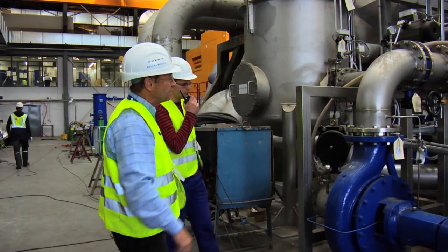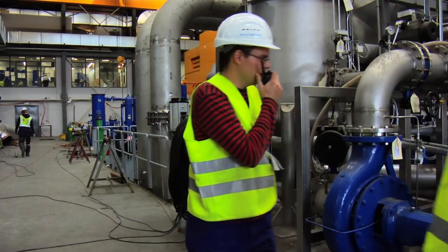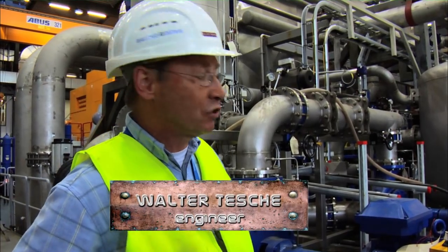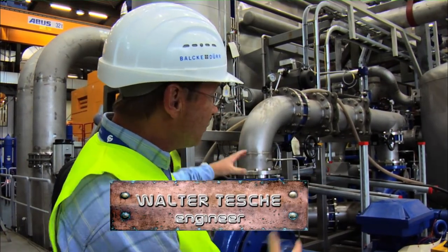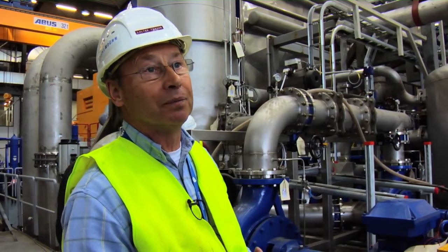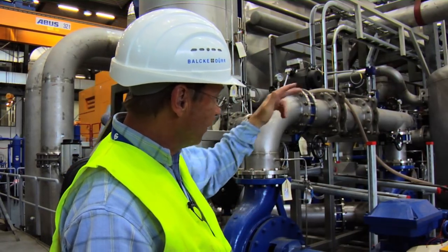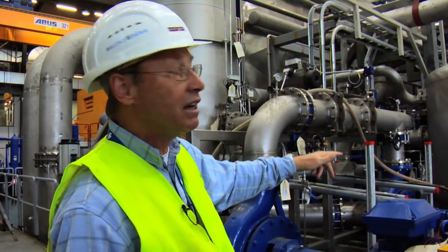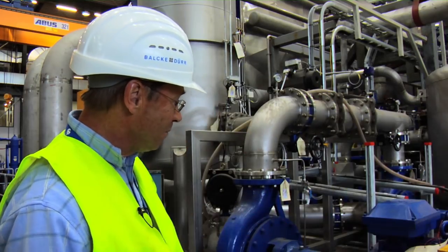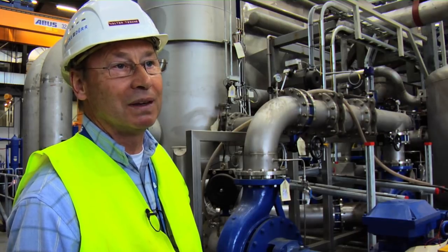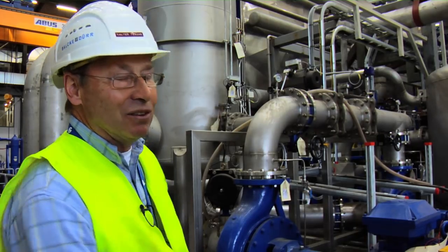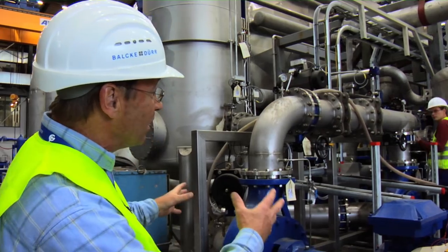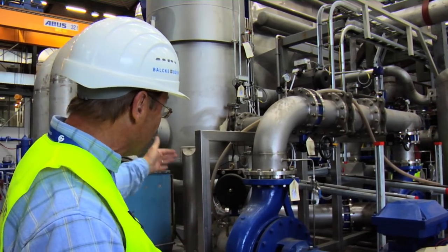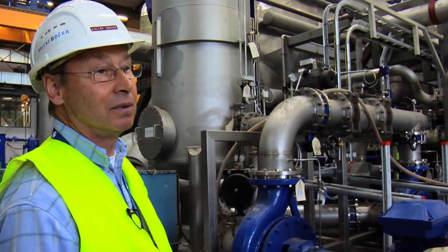One of the pumps that carries water to the cooling tower isn't working. We are starting here a cooling circuit, a small circuit with 2 parallel pumps. They are working absolutely parallel, but only one pump should work. Now we have tried it on that side. This pump is working correctly and makes a pressure of around 1.5 bars. That should be when the pump is working. And here, this pump makes a pressure of 0. That means no water is flowing, although it is absolutely parallel. We are assuming that something is wrong here on the suction side.